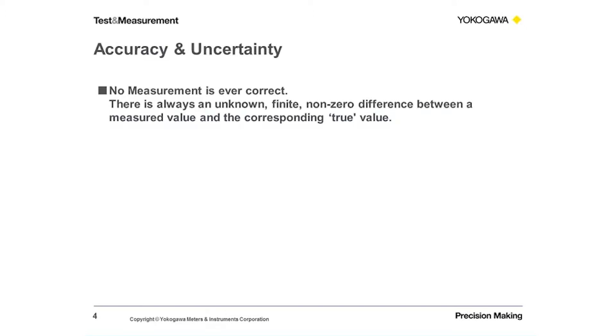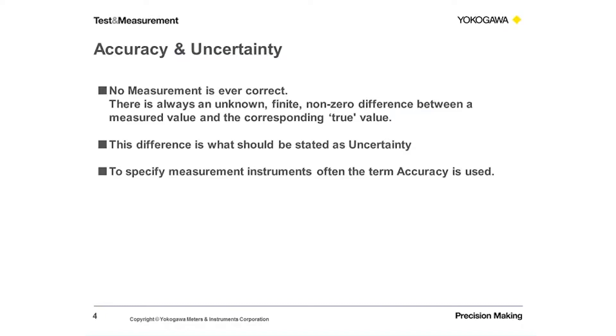No measurement is ever correct — that's why we need to specify the uncertainty. The uncertainty is an unknown, non-zero difference from the real value. However, when you look at measurement instruments, often the term 'accuracy' is used, which is more or less the inverse of uncertainty. If somebody specifies accuracy as 0.1%, that theoretically means it's 99.9% correct — which is not really a useful way to express it.